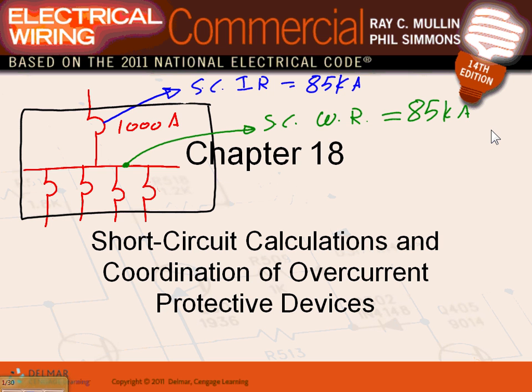The last one, guys, is the short circuit. Right here, if I short right inside this panel, that's called available short circuit. That's if I take phase A, phase B, and phase C and bolt them together. Can you imagine that? Bolt phase A, phase B, phase C together and flip the switch on. I'm going to get 81.35 thousand amp. That's called the available short circuit. Any question, guys, about these three things?